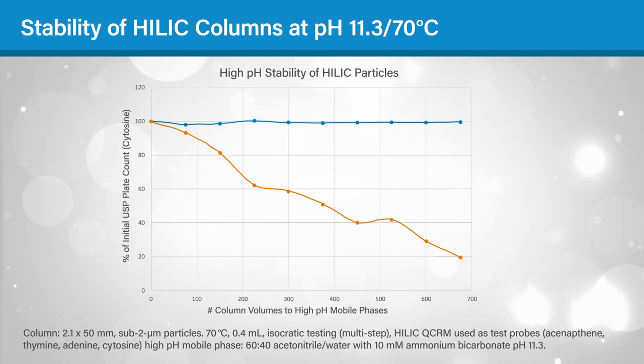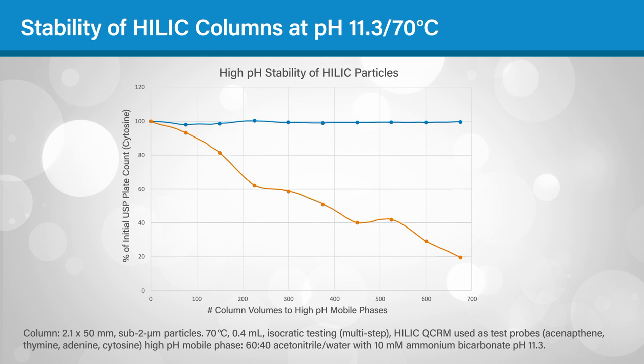Additionally, the pH stability of a stationary phase is very important. Changing the mobile phase pH during column screening can modulate selectivity by altering the charge states of the analytes and potentially the stationary phase. However, not all columns are compatible with high pH mobile phases. Most silica-based materials are not stable above pH 8 because the silica particles begin to dissolve, leading to column voiding and large efficiency losses.